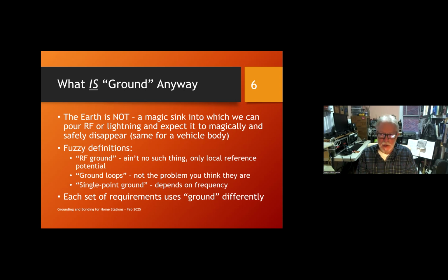Then there's the term single point ground, which came about again out of the audio and AC field. It means a connection to a point that's so electrically small that you can treat it as being all the same no matter what you connect to it—very electrically small and very low impedance. That's a very difficult thing to do at RF. By connecting all your ground wires to a single point, you actually increase the size of the ground loops associated with this stuff, making it even easier for magnetic fields and RF to cause trouble. So we're going to use the term single point ground carefully, primarily as it's associated with AC safety and lightning protection. Each of these requirements—AC, lightning protection, and RF management—uses the term ground differently, so we have to be very careful.